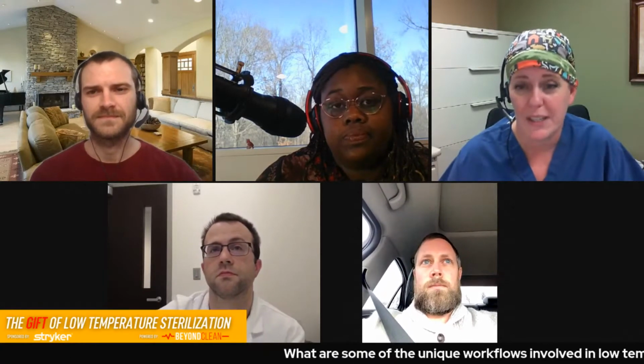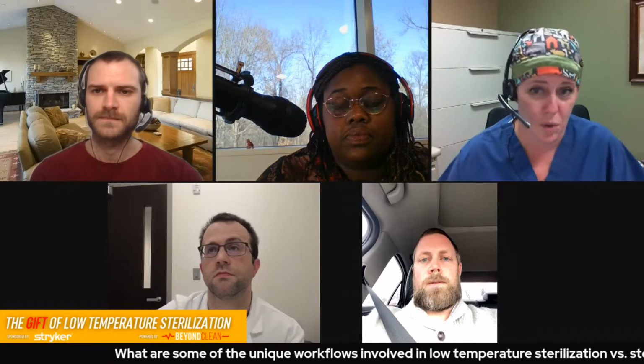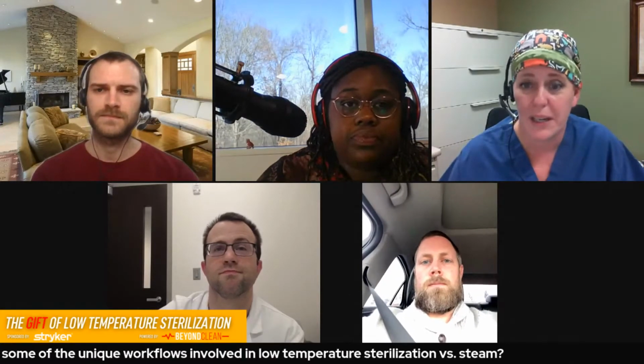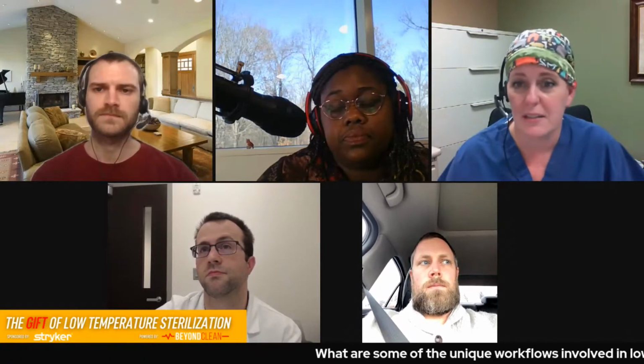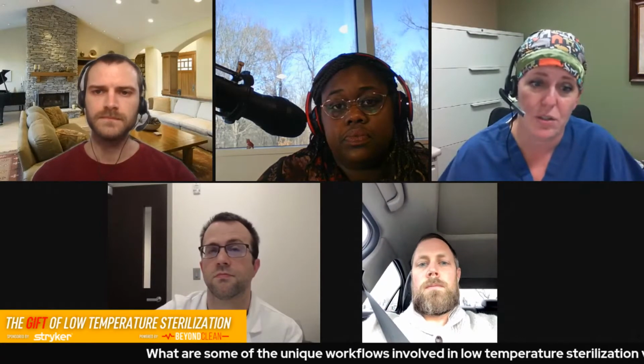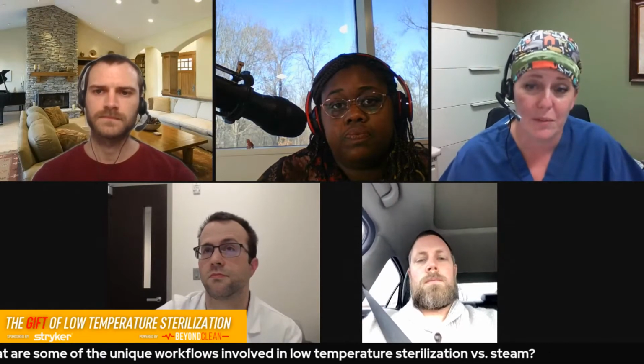I do have a couple more positives. Go ahead. The benefit it offers our patients around patient safety, the equipment we can reprocess with a terminal sterilization versus a high-level disinfection, and what this technology opens up to us. There are advancements all the time. Ozone was mentioned earlier. Some of the devices have a combined hydrogen peroxide ozone cycle and 510K clearance to do, say, GI endoscopes, or just those additional validations that low temp companies are doing with manufacturers to open it up and allow us to terminally sterilize more critical equipment for our patients. That is a huge win that we can give back to healthcare in general, and that's something I'm really proud about for us as an industry to be able to do.